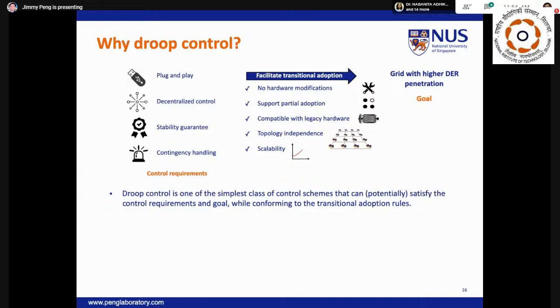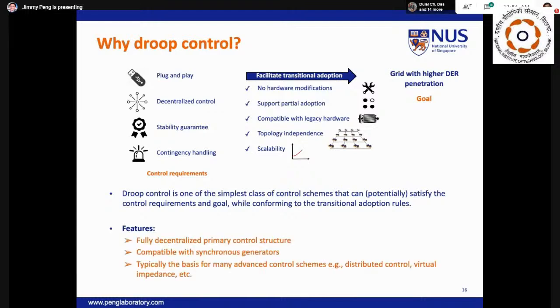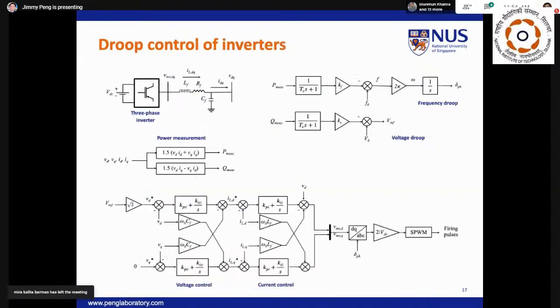That said, to facilitate more distributed energy resources in the microgrid, the control design should consider aspects of plug-and-play, decentralized control, stability, and contingency handling. The transition should not demand significant hardware upgrades and be adaptive to a range of operating conditions. So now, the task of a grid-connected mode inverter is to control current into an established voltage, whereas the task of islanded mode is to establish that voltage. Suppose we have a two-bus network consisting of one grid-forming three-phase inverter and the infinite bus as shown in the single-line diagram.